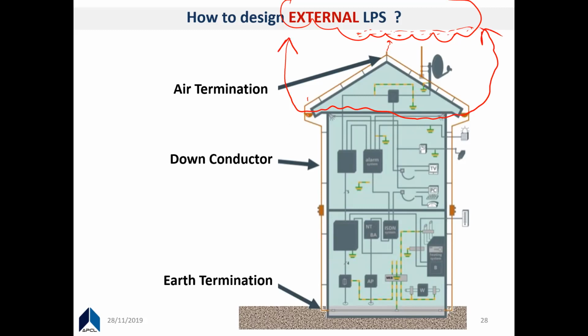And you have down conductors, where the charges that are neutralized throughout the process are delivered to the ground - that's done through these down conductors. These are external down conductors, but you might also have down conductors within the columns or other structural elements, or even the steel columns themselves could serve as down conductors, like I mentioned.